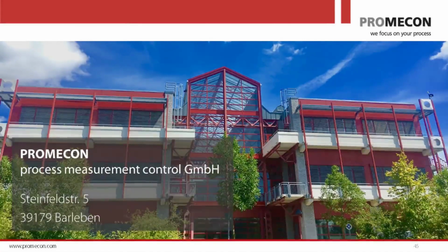But the far more typical problems that you have, let's start with secondary airflow and burners. Eyebrows over your burners, flame impingement on the boiler wall, difficulties with flame attachment. All these are typical for airflow problems. You blow out your flame, or you shoot the flame too far to the opposite wall. These are all airflow issues. Now, then, of course, everything in the combustion-related area: high airflow, high NOx, low airflow to a burner, high CO, high unburned carbon. Typical issues.